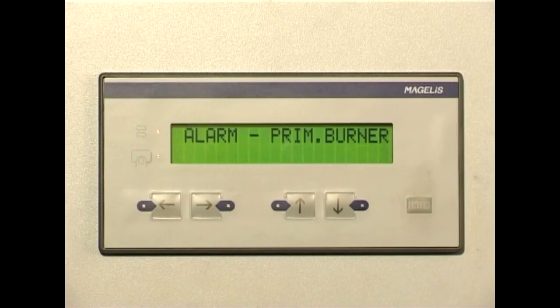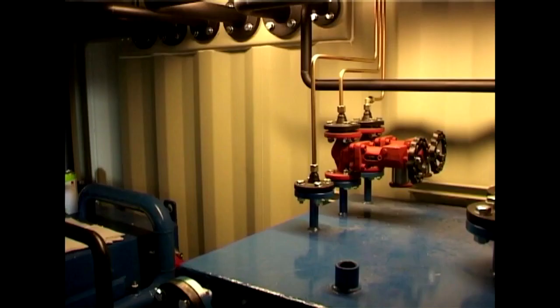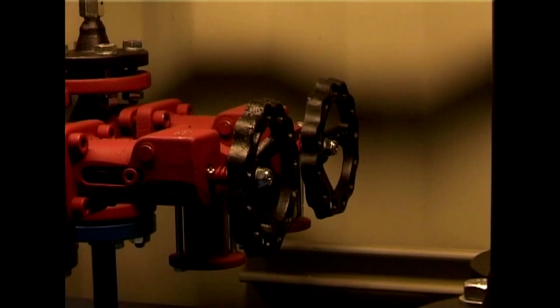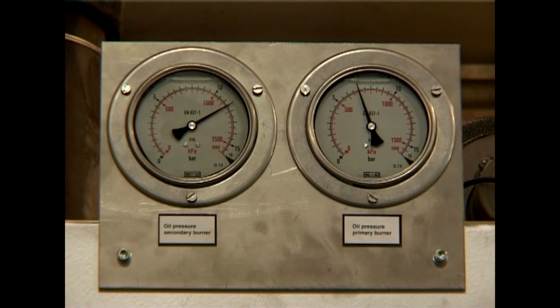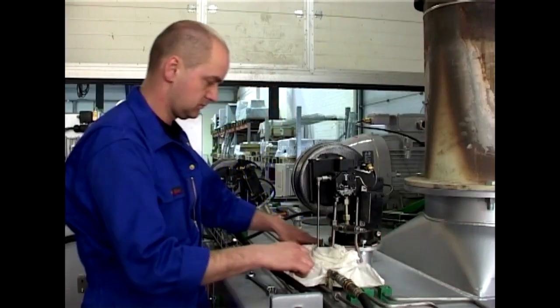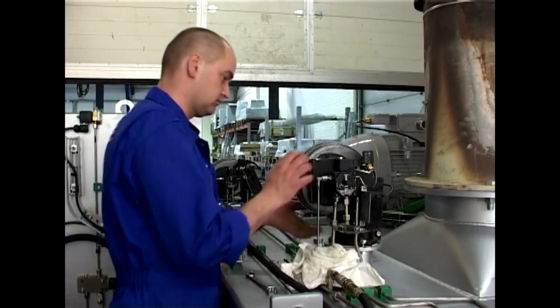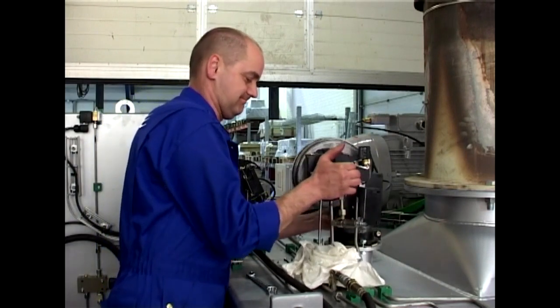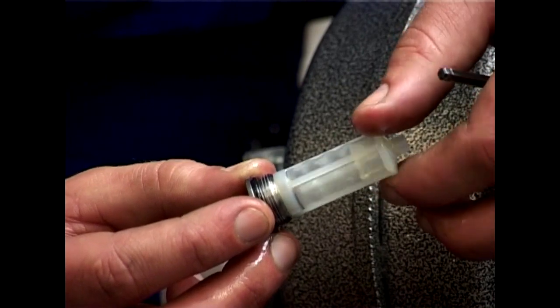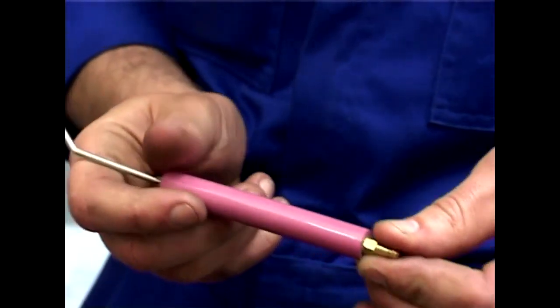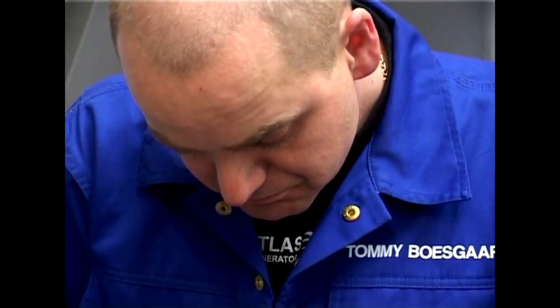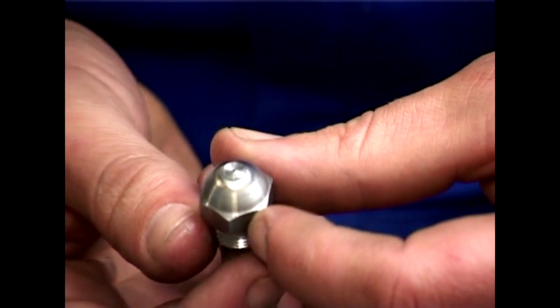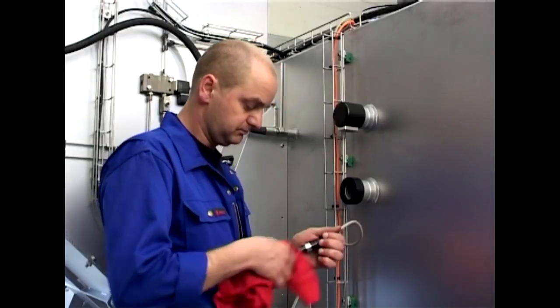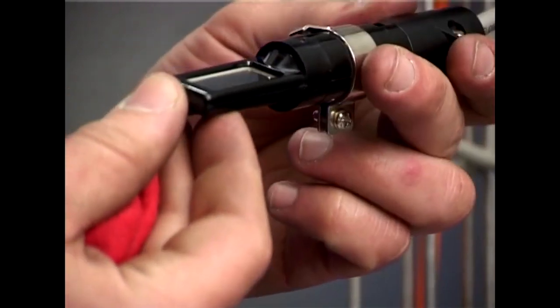The most common reason for a flame failure is lack of oil supply. Check that diesel oil is led to the incinerator and that the return pipe is open. Also check that there is oil pressure on the burner by reading the pressure gauge, which should read 10 to 12 bar. If everything is in order, the next step is to check the condition of the burner. Dismantle the burner as explained in the service section and clean the filter and check the ignition electrodes and ignition cables. Inspect the diesel oil nozzle. Also clean the flame detector for possible soot, check its condition, and replace it if required.